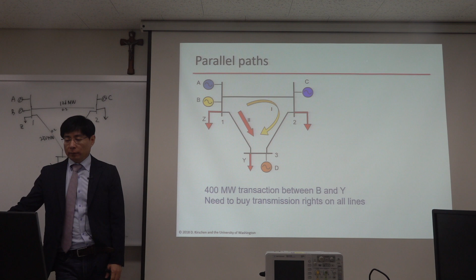When you compute the power flow you don't need to worry about other details. The impedance on this line is 0.3, and on that one 0.2, so 40% of power flows on line 1-2, which is 160 megawatts, and 60% flows on line 1-3, which is 240 megawatts.